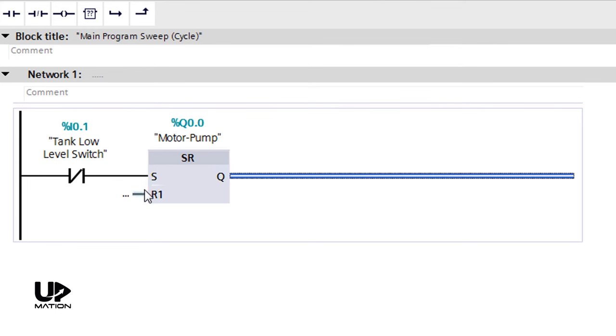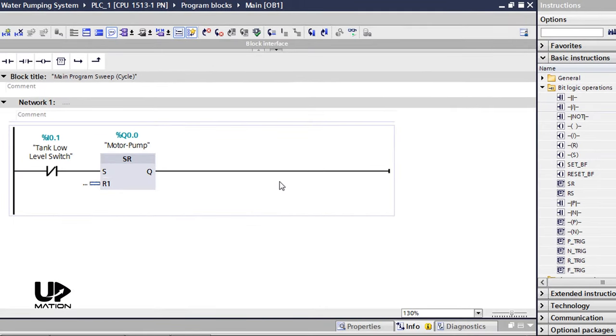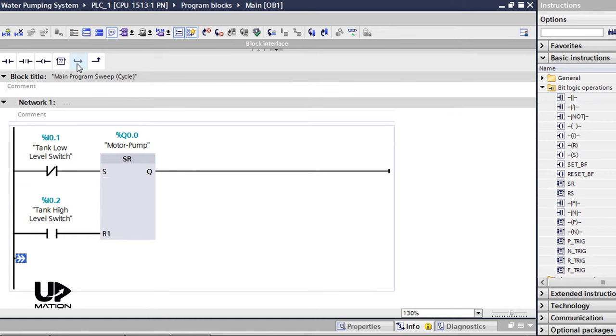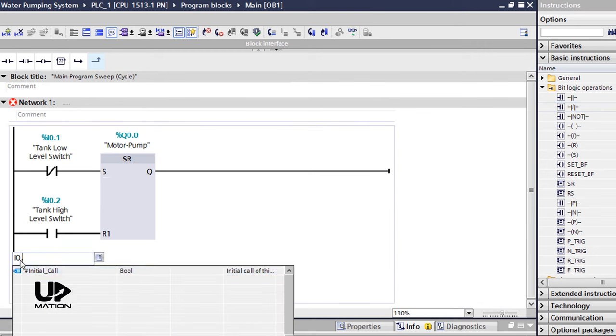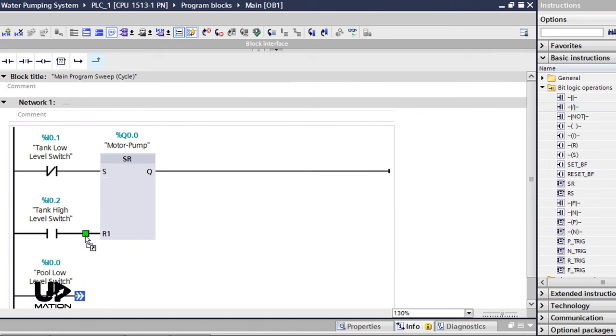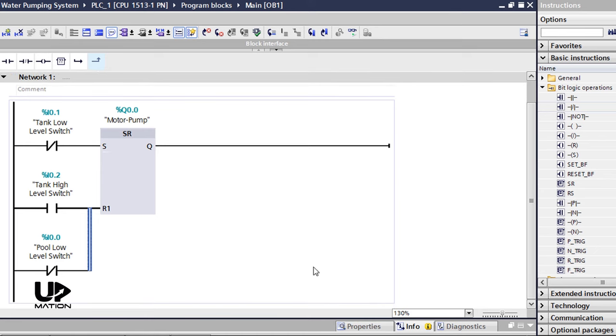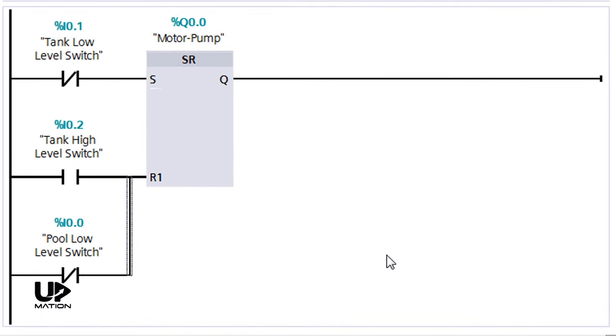As the next step, I click the reset input of the flip-flop and connect an open contact to that for the I0.2. To continue, I use the open branch and add a close contact for I0.0. This way, we will shut down the electric motor whenever the water level reaches the low level in the pool or the high level in the tank.